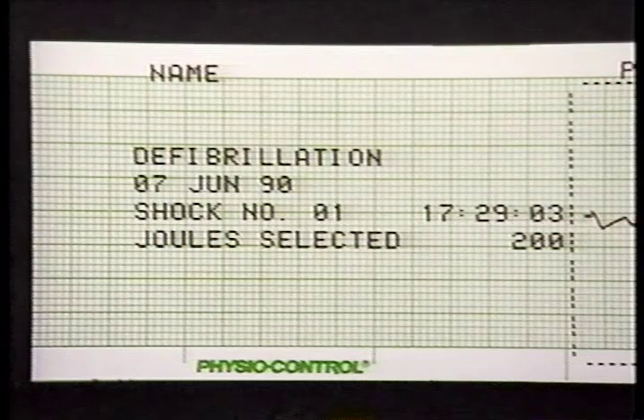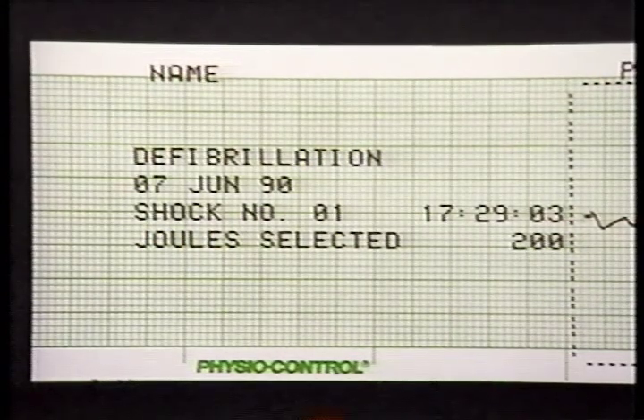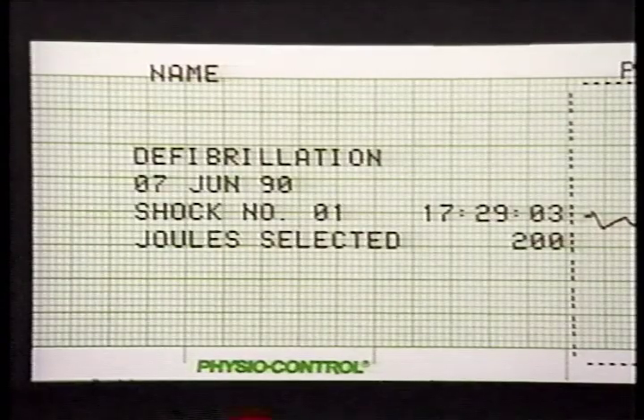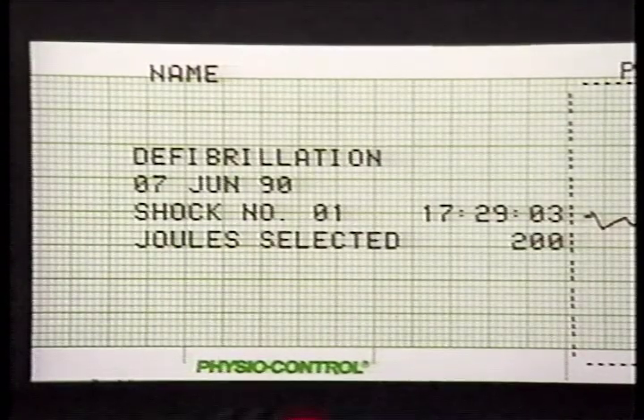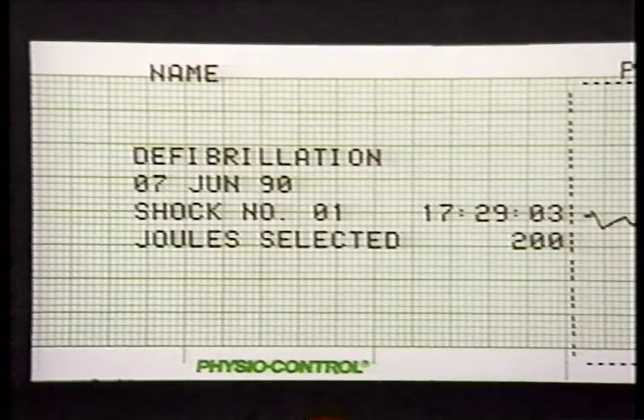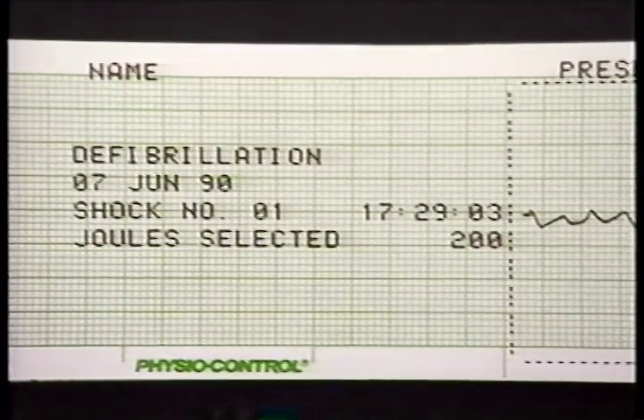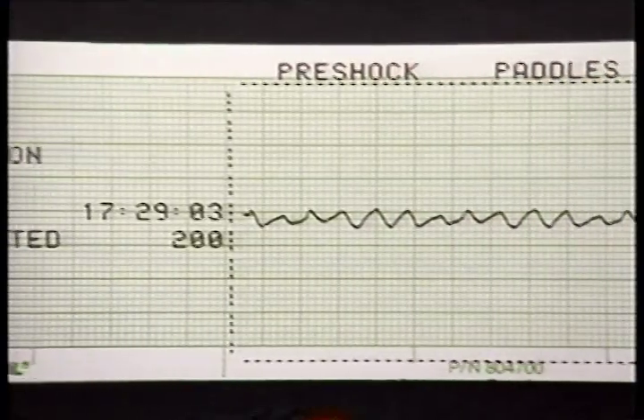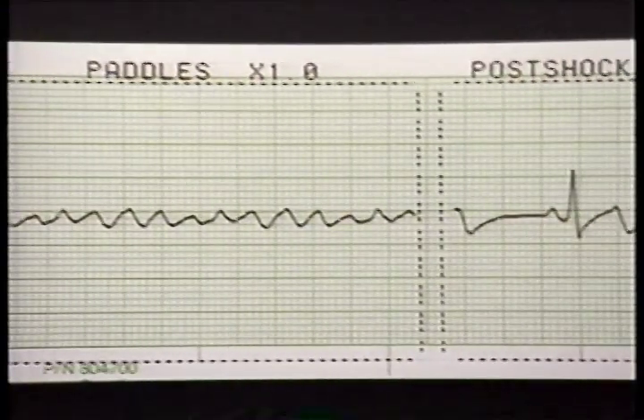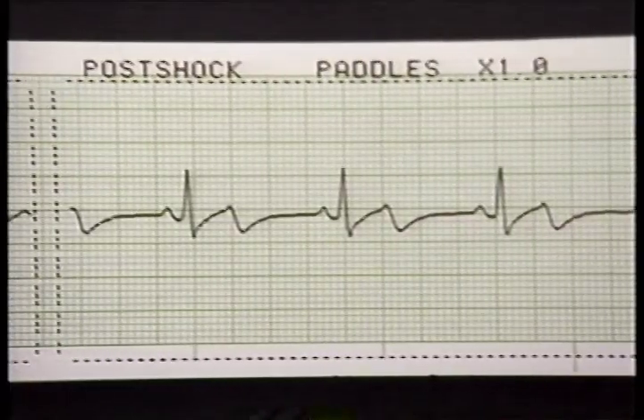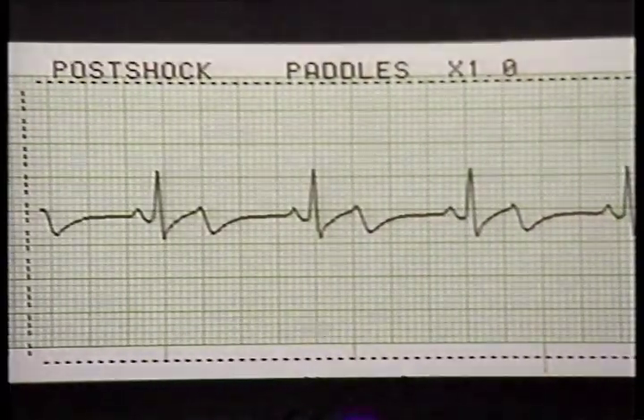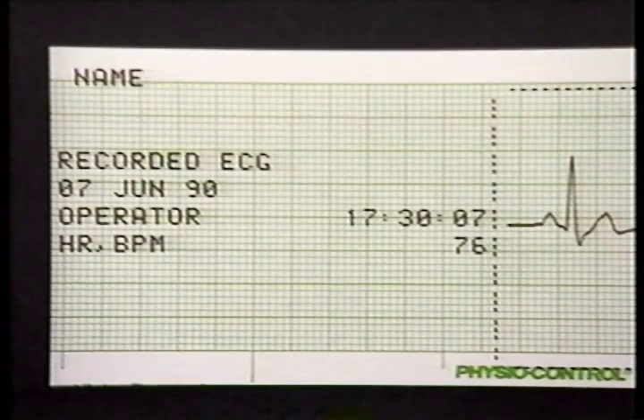The defibrillation format is printed for each shock delivered. The information preamble includes a space for the patient's name, a defibrillation label, the date, the sequential number of the shock and the time of the energy delivered, the number of joules selected, and a sync mode label for synchronized shocks. Following the preamble is 3 seconds of pre-shock ECG and 6 seconds of post-shock ECG, annotated with lead and gain settings.